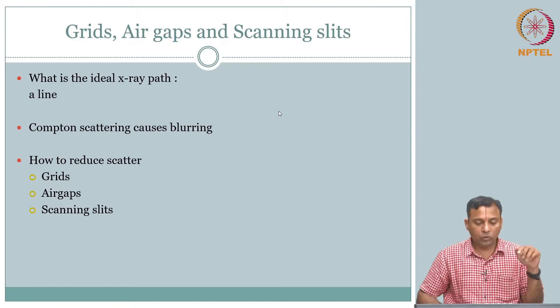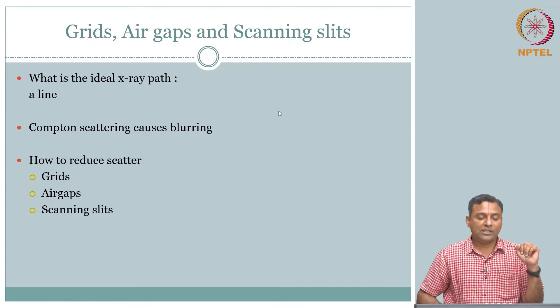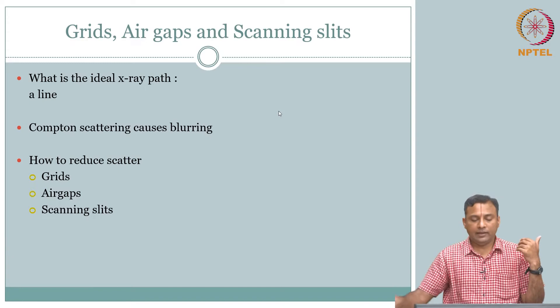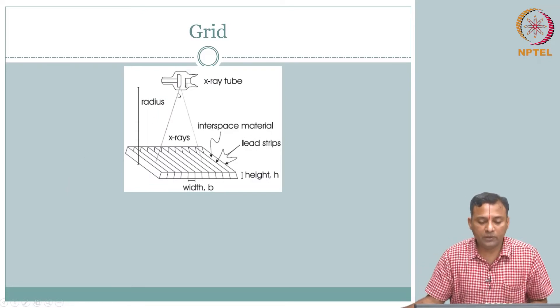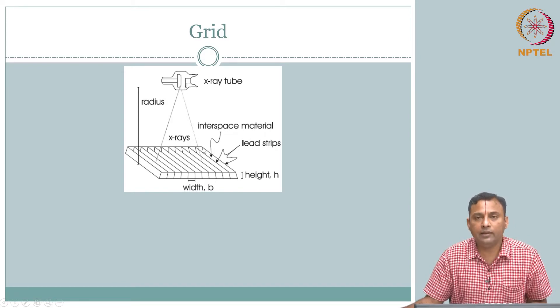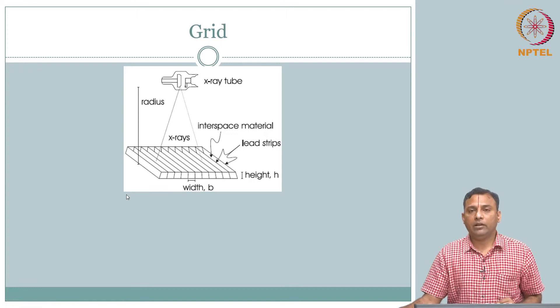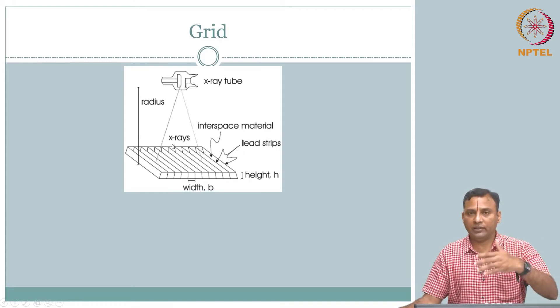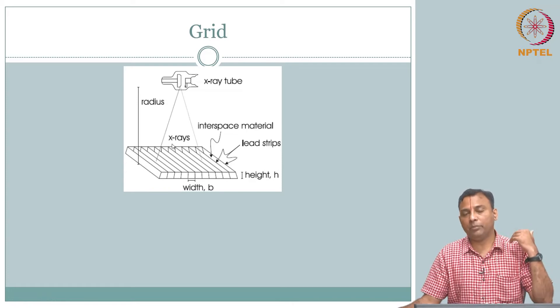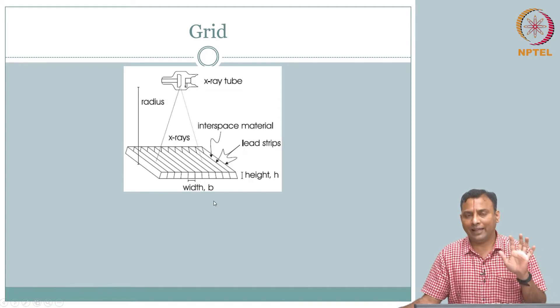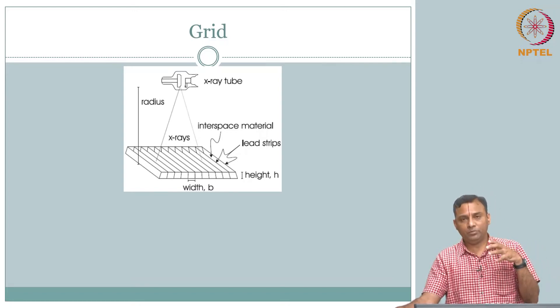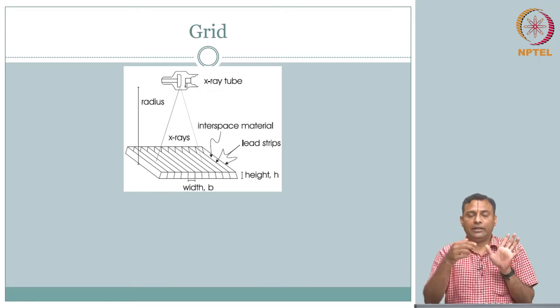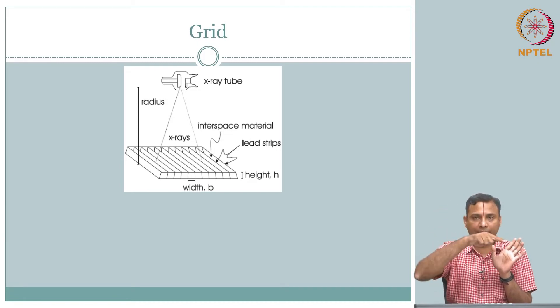How to reduce scatter — there are three ways. For a grid: you have lead strips organized in a grid pattern placed between the patient and the detector. After it passes through the patient, you are going to have scattering. The x-ray source sends a diverging cone, and the lead grid is focused — tilted so the slits align with the diverging line of sight from the source. The transparent gaps between the lead strips allow the straight-line photons through; photons coming at a different angle due to Compton scattering hit the lead and get absorbed.